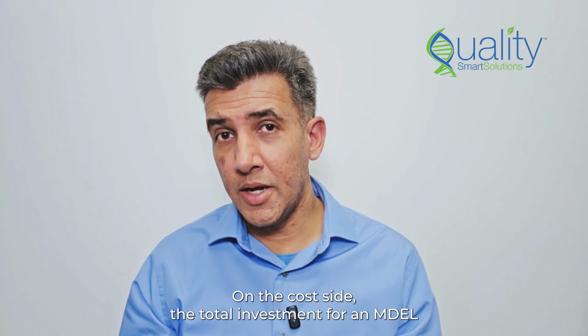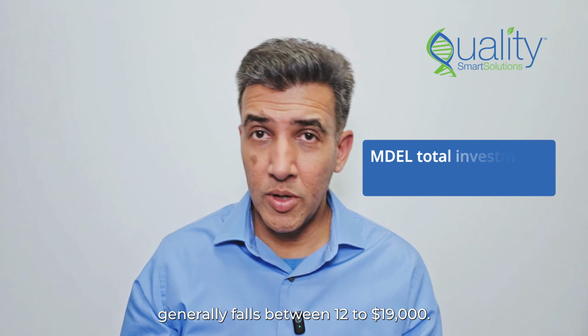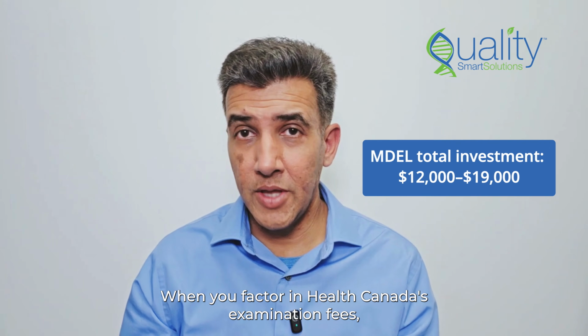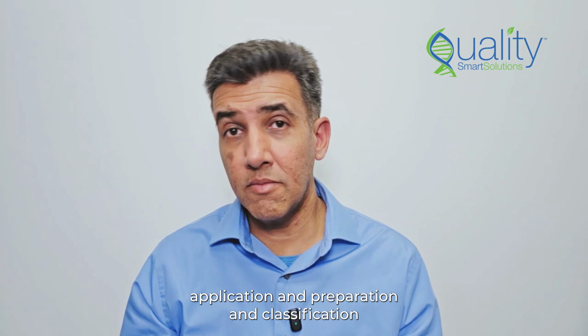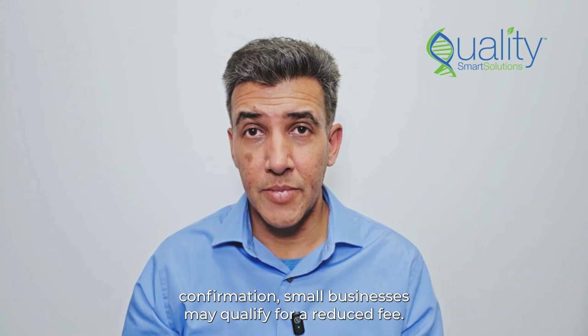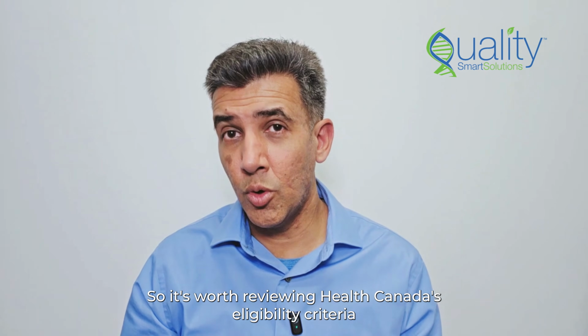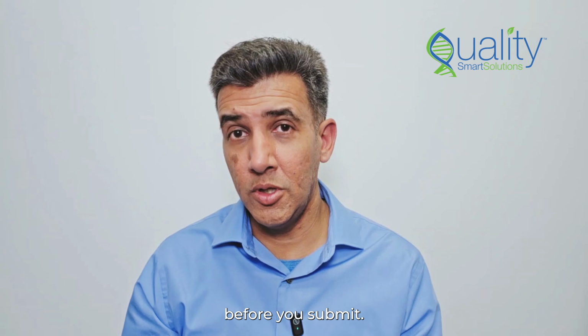On the cost side, the total investment for an MDEL generally falls between $12,000 to $19,000 when you factor in Health Canada's examination fees, application and preparation, and classification confirmation. Small businesses may qualify for a reduced fee, so it's worth reviewing Health Canada's eligibility criteria before you submit.